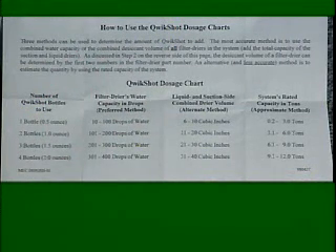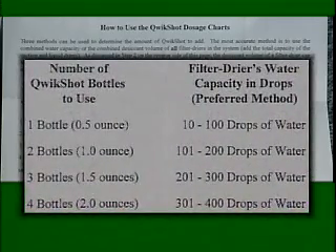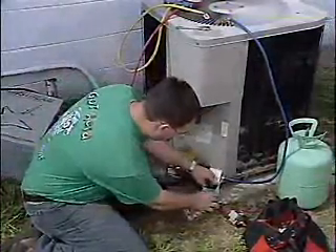One box of QwikShot contains four half-ounce bottles. The QwikShot dosage is calculated from the system's filter dryer size. Excess QwikShot will not harm the system but does not accelerate the acid treatment. QwikShot is introduced into the system with a quick injector.